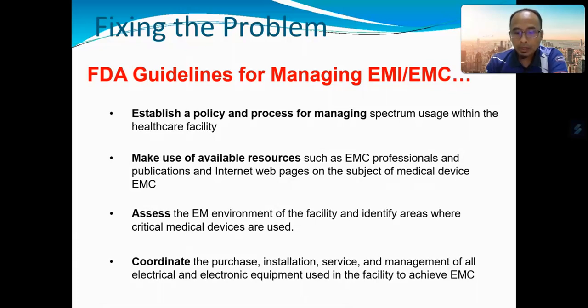What this means is that we can set up formal rules for how wireless devices such as Wi-Fi, Bluetooth, and telemetry are used in the hospital. By having this kind of rules setup, we can prevent interference between the medical equipment and RF sources like phones, routers, and walkie-talkies.